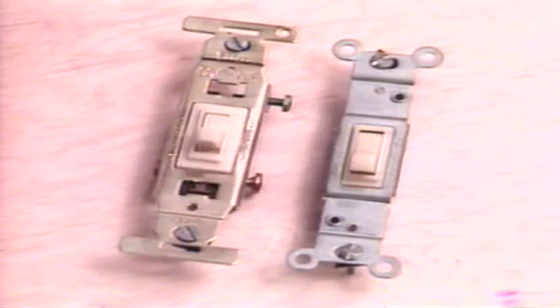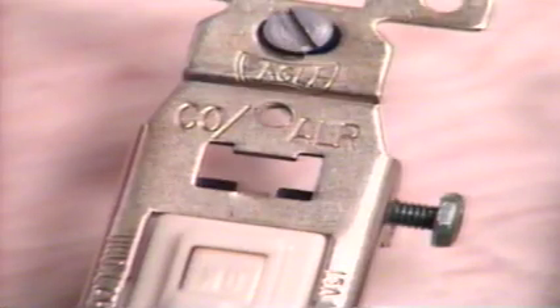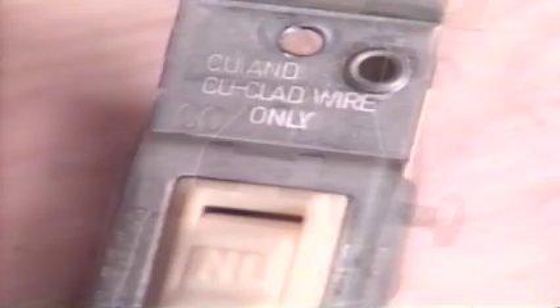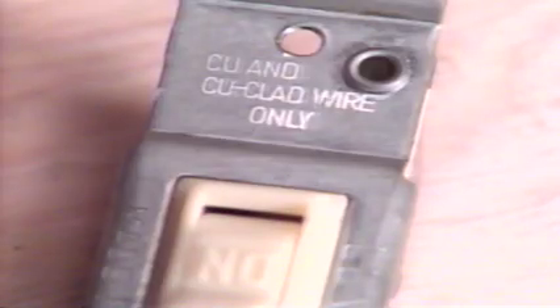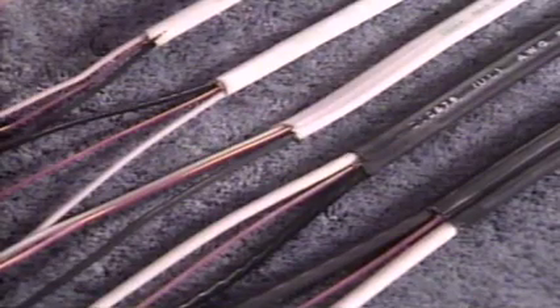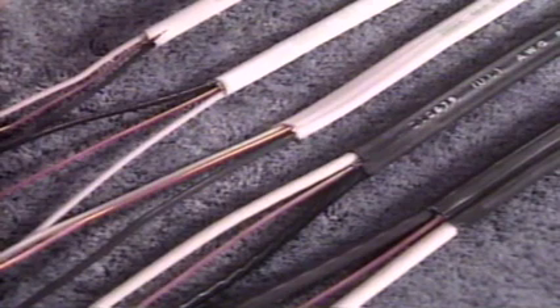The National Electrical Code requires that all terminals and connectors be marked to show the type of wire that is allowed for use. A connector marked CO/ALR means that copper, aluminum, or copper-clad aluminum wires could be used. If a terminal is not marked with an AL or a CO/ALR, then only copper or copper-clad wire is acceptable for use. Typically for residential electric wiring, non-metallic sheathed Romex cable is used.